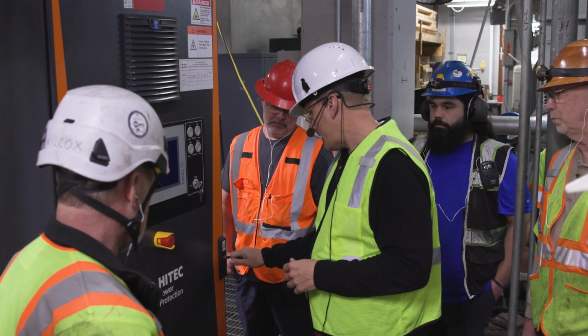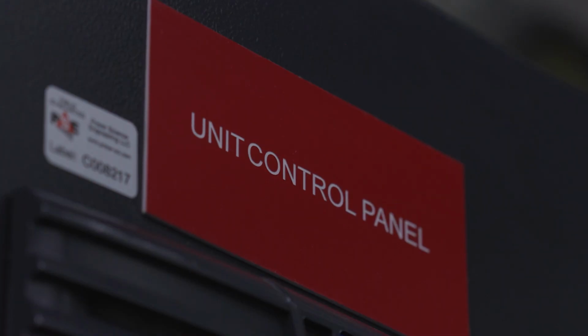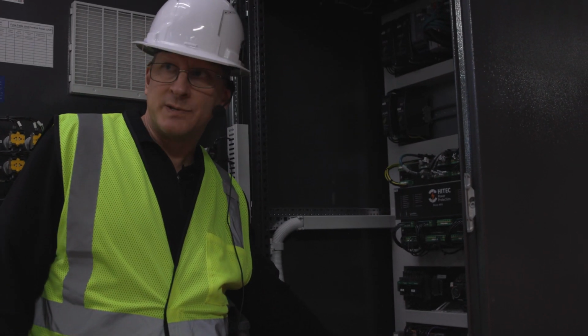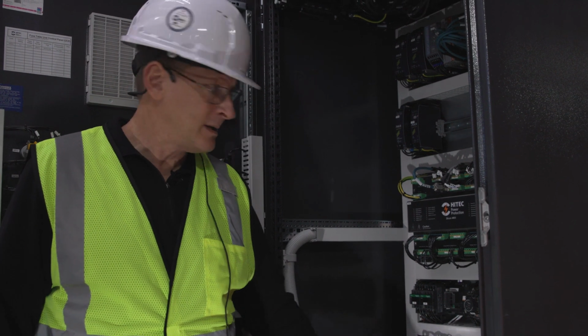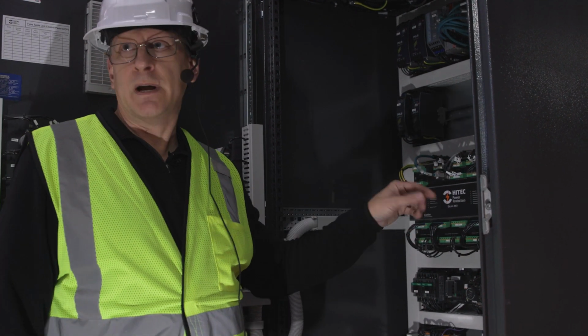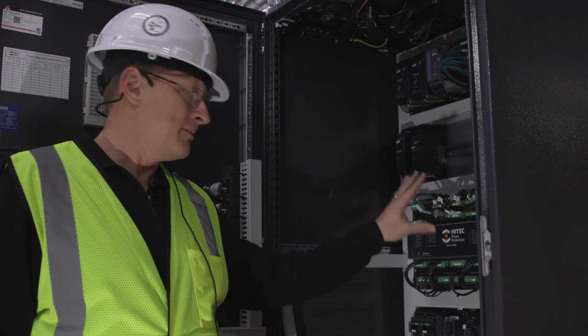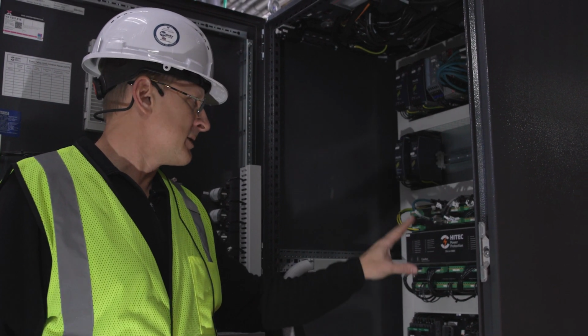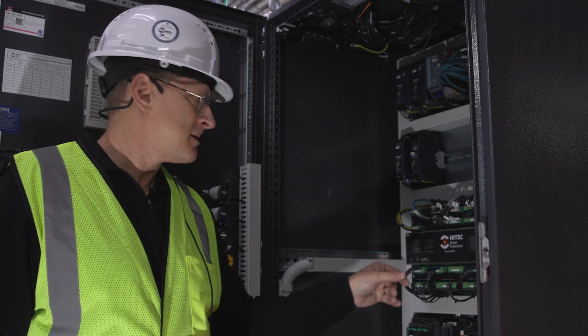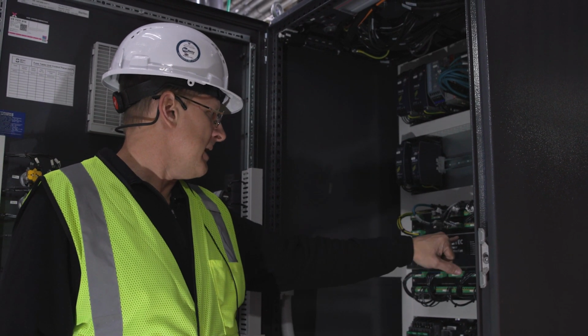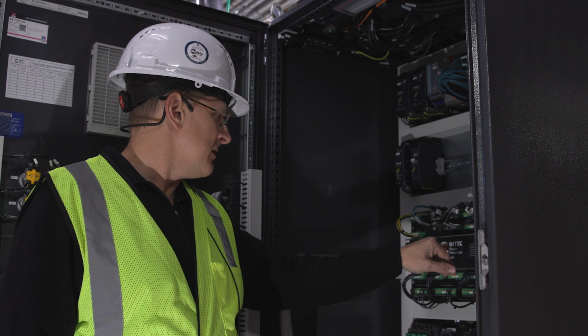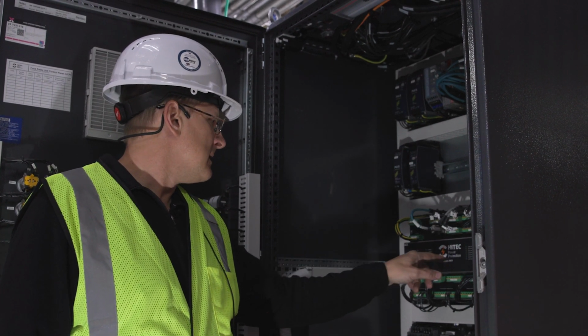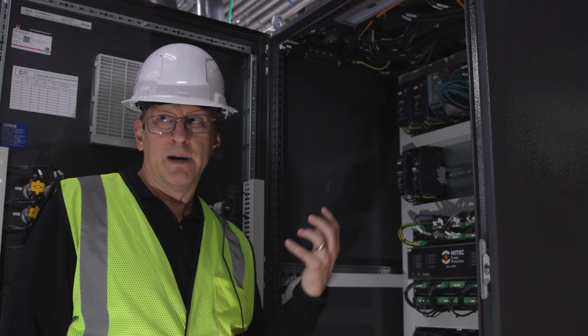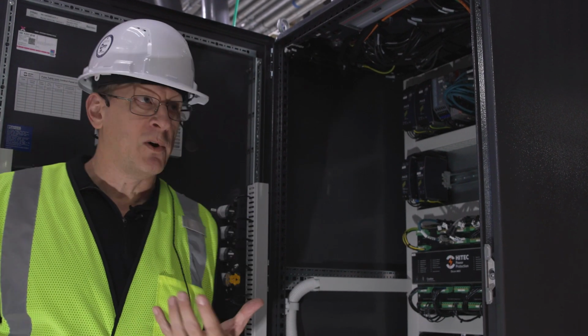Let's take a peek inside real quick. In our UCP cabinet, again, this is our PLC. It's the brains of the unit, the whole operation. This is our Dicon Mark II, what I mentioned in training. This is the heart of our system. So this is our monitor, controller, protective device. And you'll notice I mentioned it has some light indications on it. So it'll give you certain indications of health, power. It'll give you indications of utility voltage and frequency, load voltage and frequency.